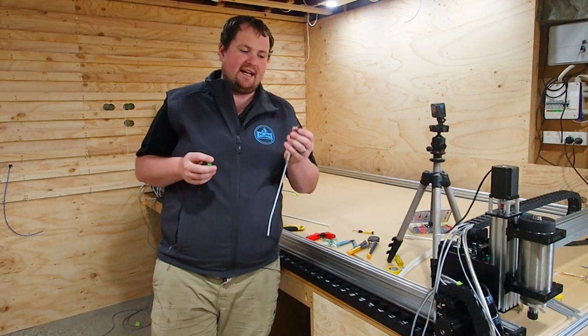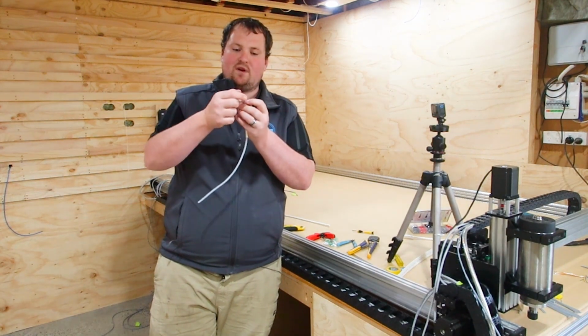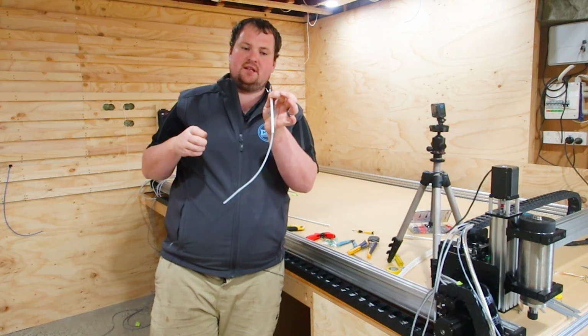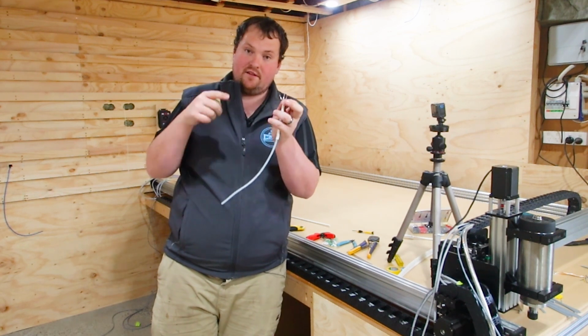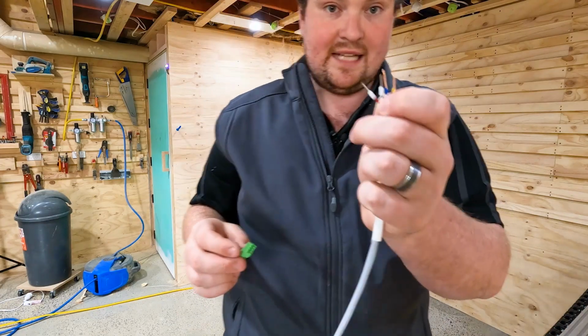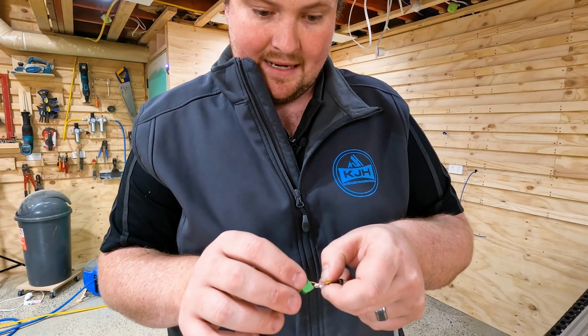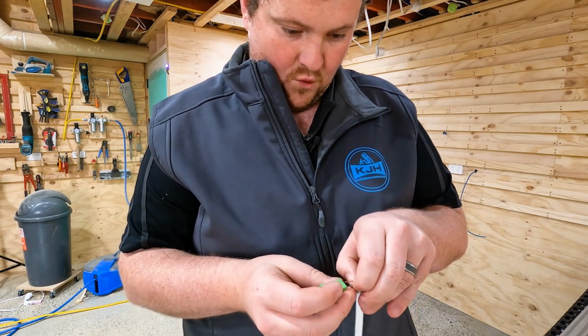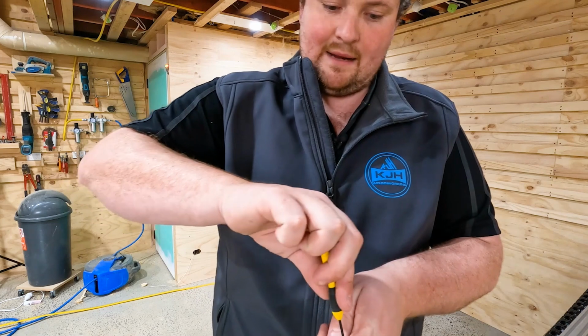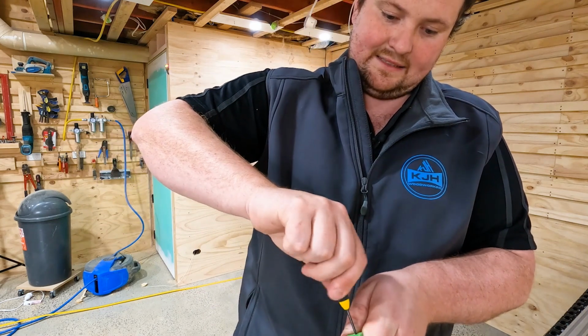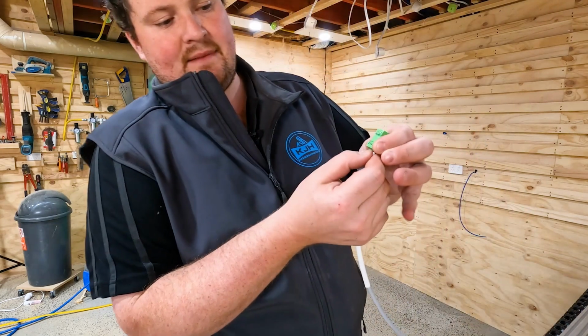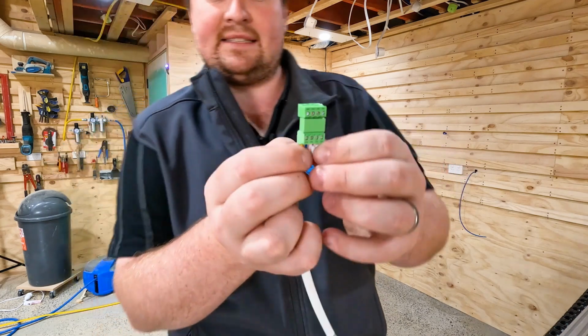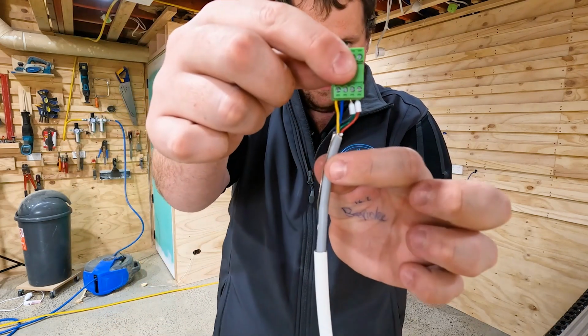Now the order of connection for your cables is red, green, blue, yellow. I'm going to use half with my ferrule, half without for the demonstration, but all you're going to do is take those 4 points, put them in each of the 4 connections, tighten up your screws so they're nice and snug. Then we're going to do a tug test to make sure we can't pull those out.